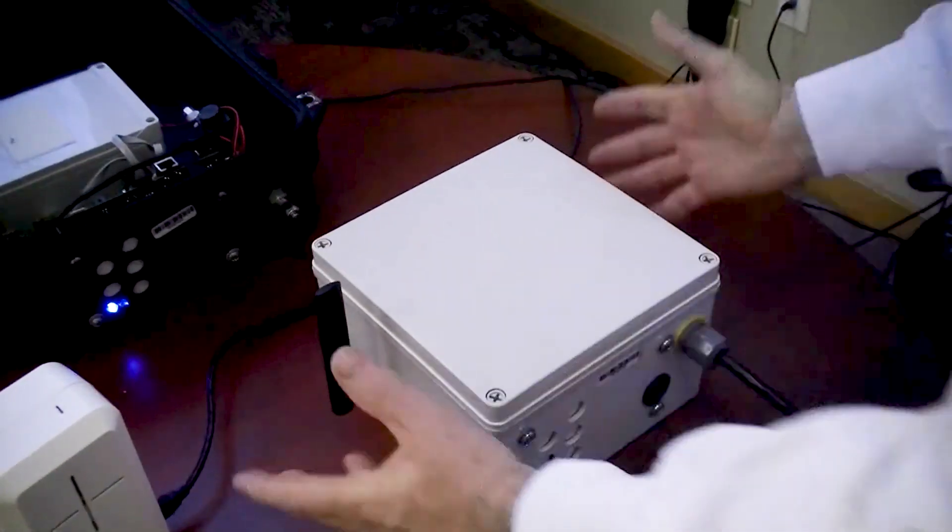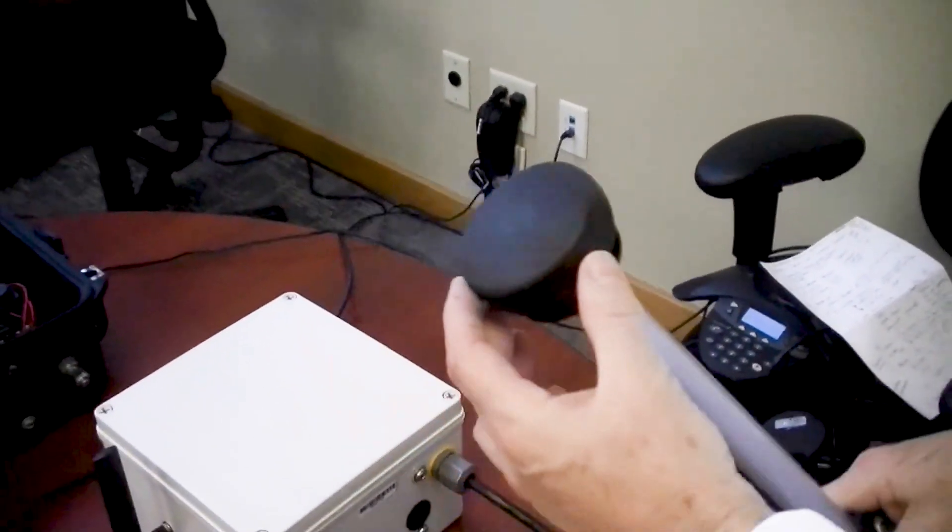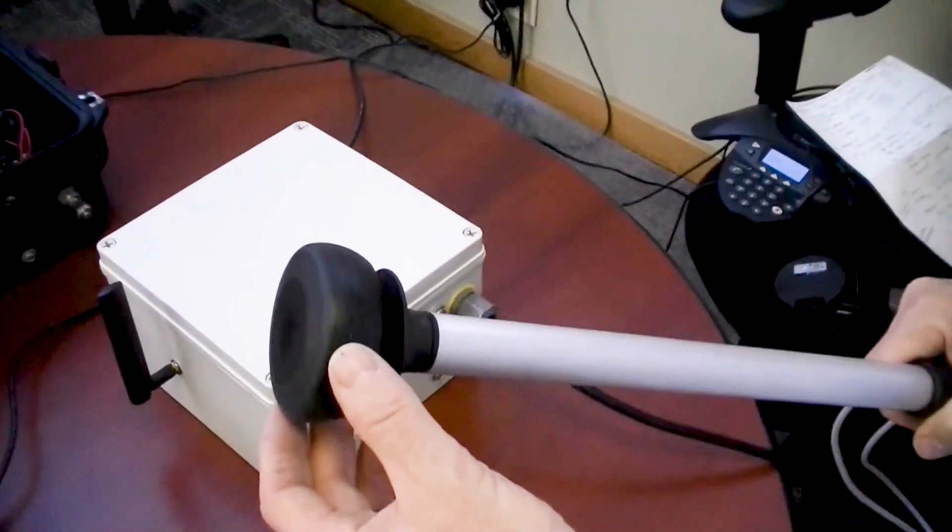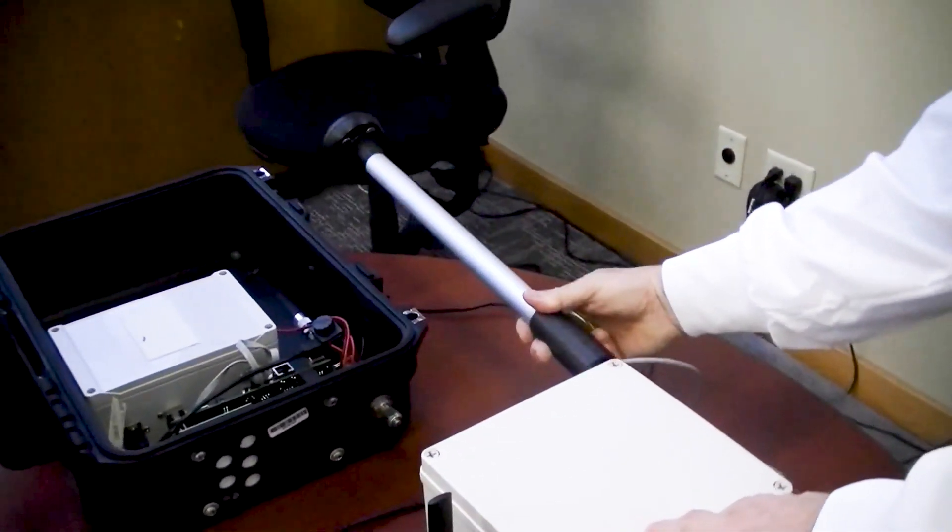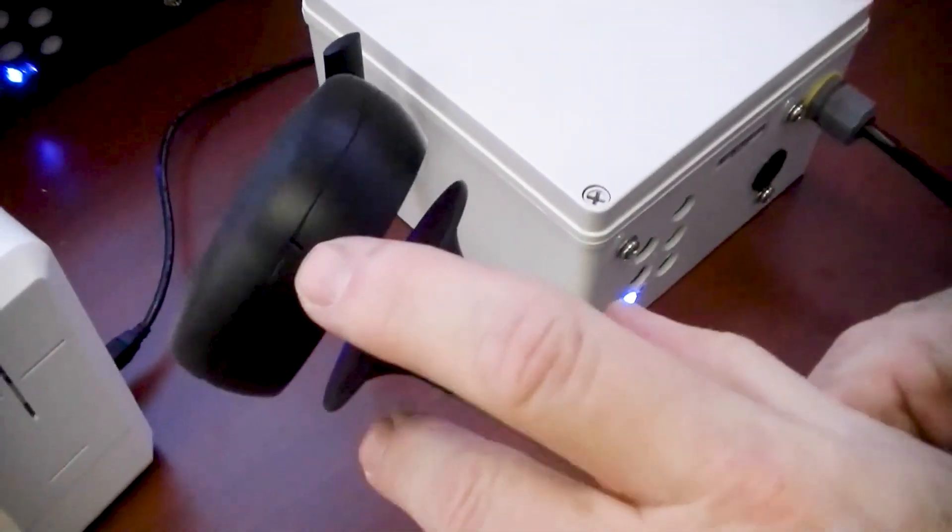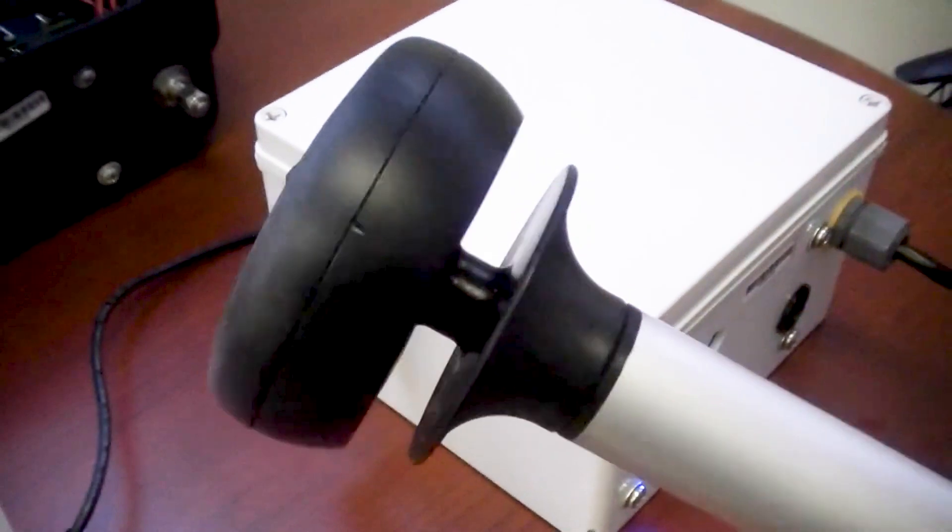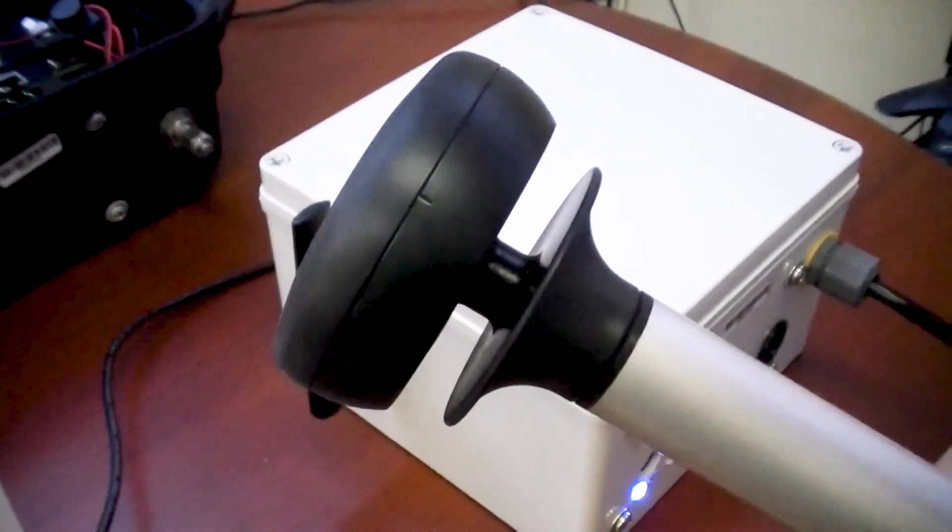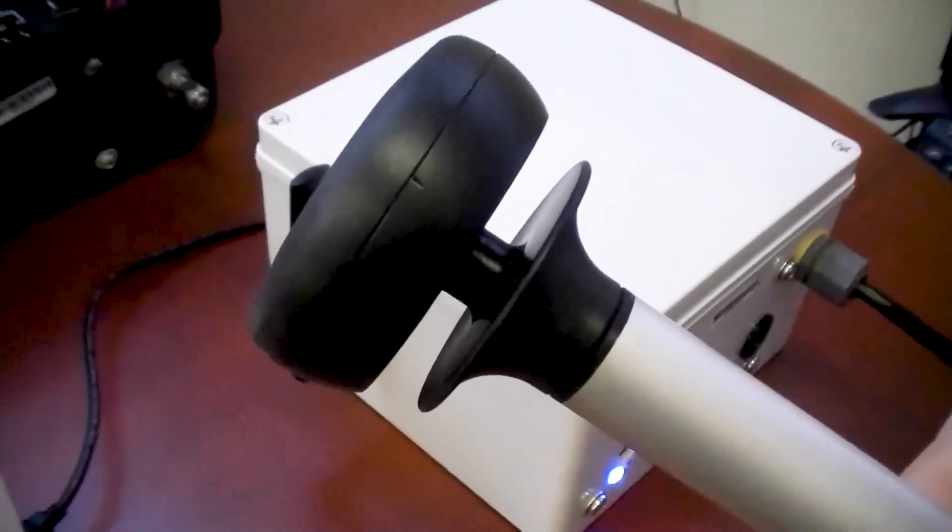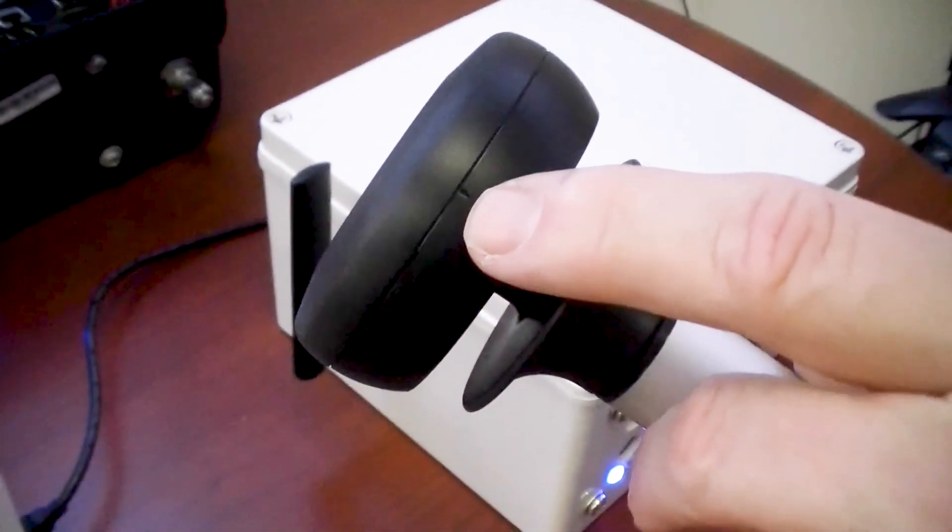Basically it's plugged the unit in and it starts up. For outdoor devices we also have this sensor available. This is an anemometer that does wind speed and direction. These have been oriented or mounted on these devices as well as on the sample capture box or they could be remote mounted. On this wind speed device there is a small nick in the plastic that indicates when it's installed, even if it's mounted onto one of these two cases, this notch needs to point toward north so that we reference the direction properly. It's best if you can make this point directly due north.